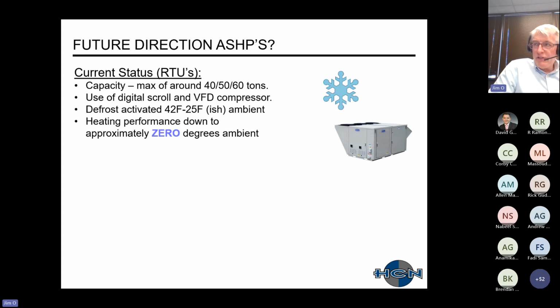There are custom refrigeration manufacturers. The ones that come to mind are Annex Air, Nortec, probably some other ones as well. That probably could go with larger tonnages for air source heat pumps. They're currently using digital scroll and VFD compressors. Your defrost gets activated at those ambient temperatures. I like to use the word "ish" for everything as approximations. People make fun of me, saying it's not proper English. But anyway, heating performance, typically it's down to about 0. Below that, you end up not being able to get selections because your ambient temperature is basically too low.